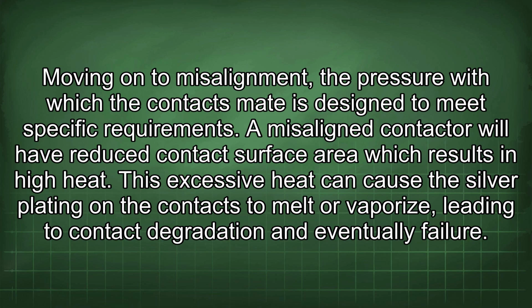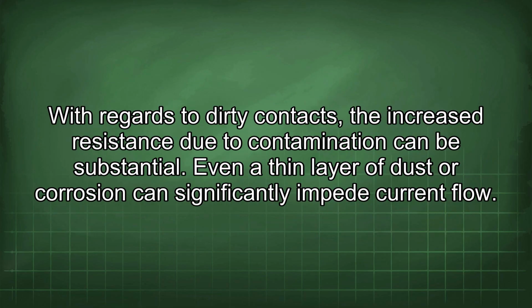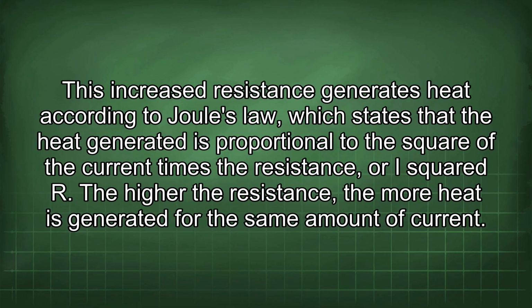This excessive heat can cause the silver plating on the contacts to melt or vaporize, leading to contact degradation and eventually failure. With regards to dirty contacts, the increased resistance due to contamination can be substantial. Even a thin layer of dust or corrosion can significantly impede current flow. This increased resistance generates heat according to Joule's law, which states that the heat generated is proportional to the square of the current times the resistance, or I squared R.